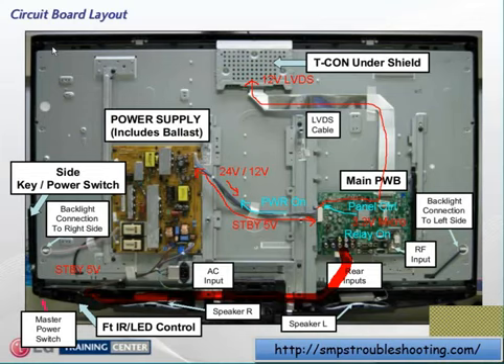The next command that leaves the microprocessor and goes up to the power supply is a command called INV on, inverter on. That now energizes the ballast, fires the ballast up, and outputs on the backlight cables.